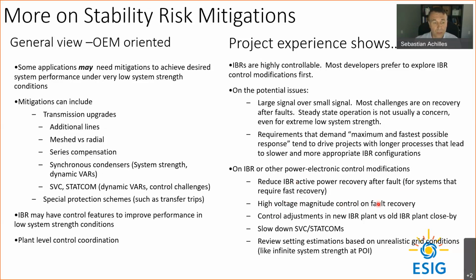When you clear a fault in a weak grid system, you tend to have high voltage. Absorbing reactive power to avoid the high voltage, but not absorbing too much to create a voltage collapse, is a non-unusual subject. Control adjustments of new plants versus old plants that are already there is also becoming more common. You connect a new project next to an old project, and when you make the grid weak for everybody, including the old project, having to do control adjustments considering that older equipment is actually relatively common these days.